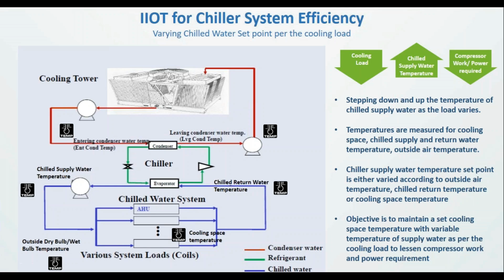Once the cooling load is established from these criteria, we can look at the real-time chilled supply water temperature, and if there's a case to increase it, we can do that remotely in real time without manual intervention. The idea is that for a reduced cooling load, increasing the chiller supply water temperature results in less work for the compressor, and hence energy saved.